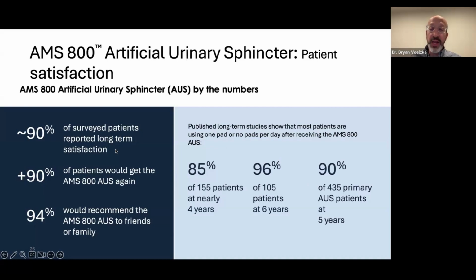And when these devices fail, they don't fail in the closed position. The tubing just breaks, and then the saline that's in the device just leaks out. And now all of a sudden, when they try to squeeze the pump, nothing's happening. So all of a sudden now they're incontinent. And these are the guys that want you to get the device put back in as quick as you can. They want to go back to where they were before.